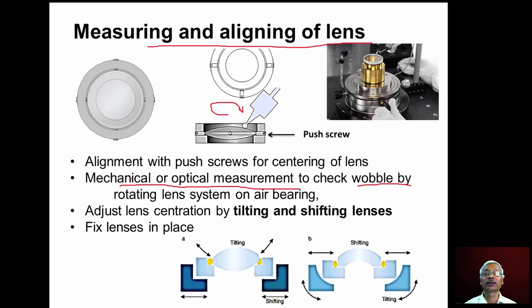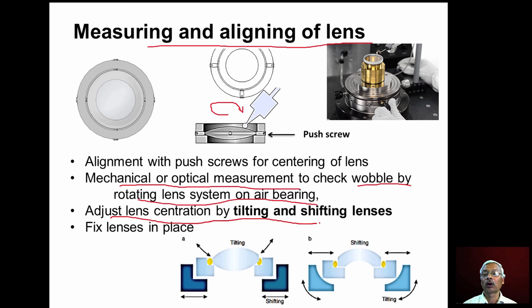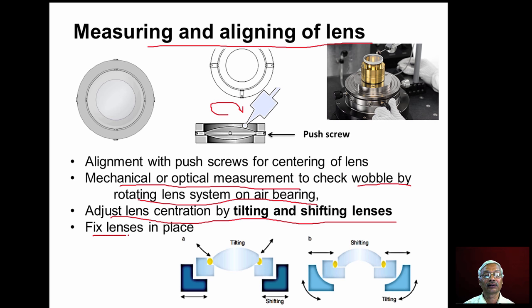A dial indicator is a simple mechanical measuring unit; we can also use a feeler gauge. The rotating lens system is normally mounted on an air bearing so that out-of-plane movement is reduced. We slowly rotate the lens system and measure the wobble. If wobble exists, we must adjust lens centration by tilting or shifting the lens, or shifting the barrel.